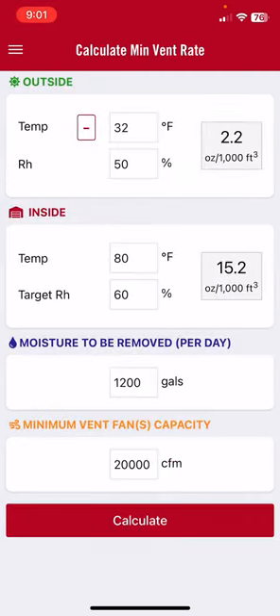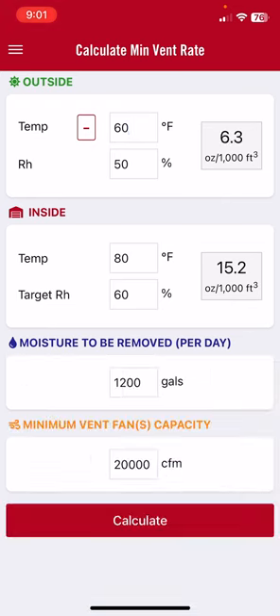We can go back and change the outside conditions. Let's say it's a much warmer day — 60 degrees and 50 percent humidity. The absolute humidity goes up because the warmer it is outside, the more moisture the air can hold. The more moisture it can hold outside, the more we have to ventilate, because the difference between inside and outside humidity is going down.